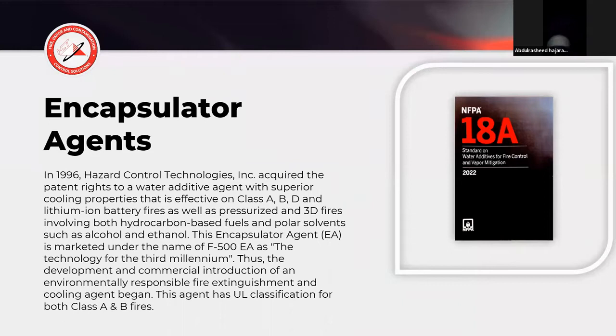But yet, when we've been unable to extinguish some of these difficult fires at our refineries or at our manufacturing facilities or other areas, what do we do when water doesn't work? We use foam. And foam doesn't work because we're dealing with a three-dimensional fire, probably 95% of the time. And in the standard, it states that's not what foam's designed to do. So let's learn about encapsulator agent and how it's different and how it's able to work on those.